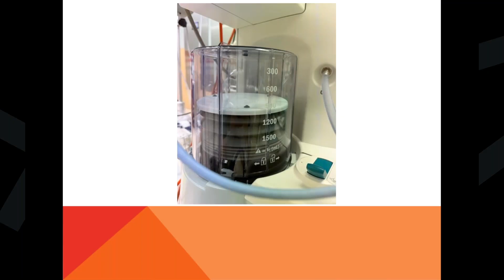Another big part of the breathing circuit is the absorber. What the absorber is, basically, is soda lime in a canister. Pretty much a big chunk of the machine. If you've worked around anesthesia or been in the OR, you'll probably know what the absorber is. Basically, the job of the absorber is to absorb the exhaled CO2 from the patient. And then in time, as the absorber gets used, it changes color, normally purple, to alert the anesthesia tech when they need to be changed.